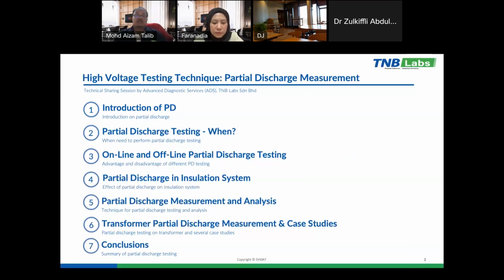So what I will cover today in this topic is the introduction of partial discharge, when we need to perform partial discharge testing in the lab and also at sites. What are the advantages and disadvantages of online and offline PD testing? Sometimes we need to test PD by the online method, and sometimes by offline methods.